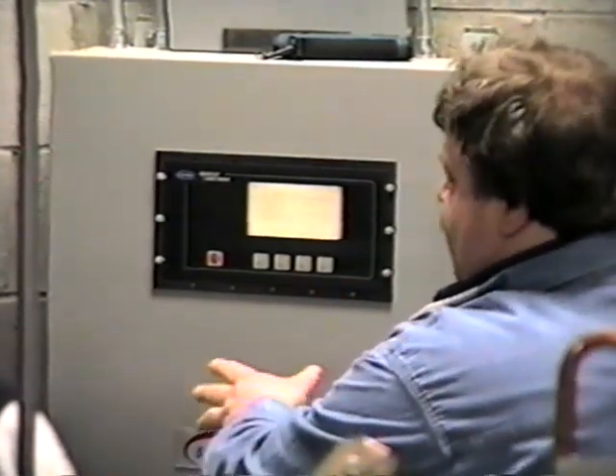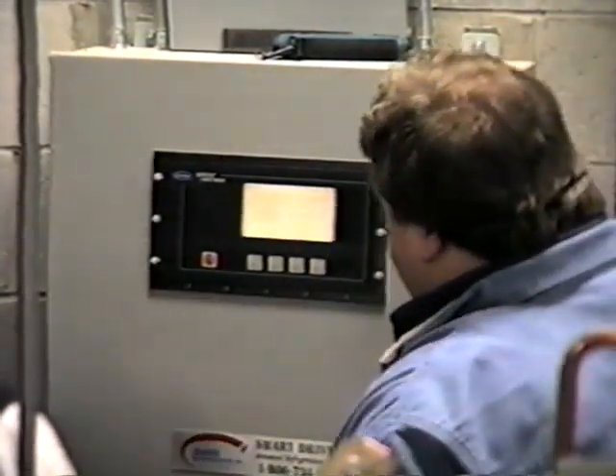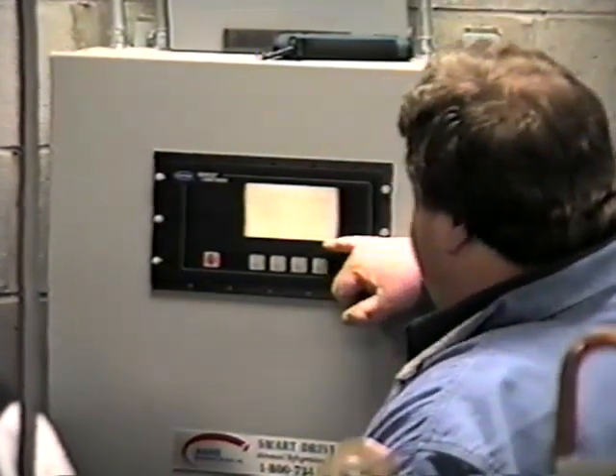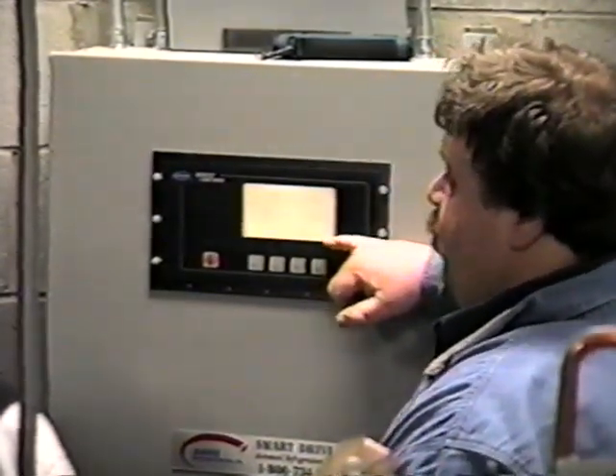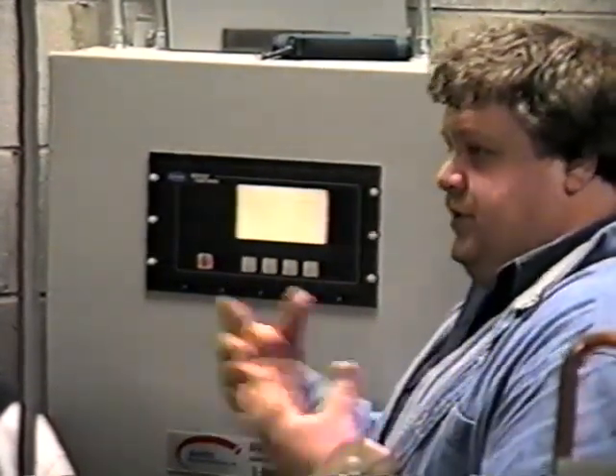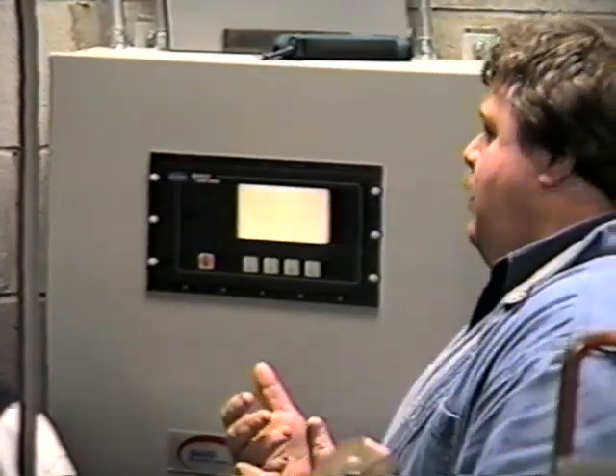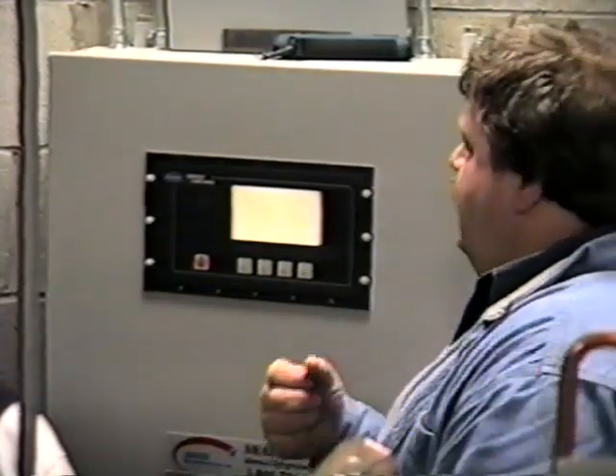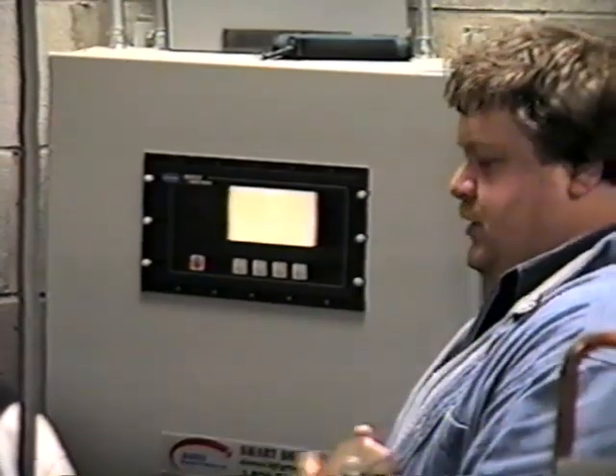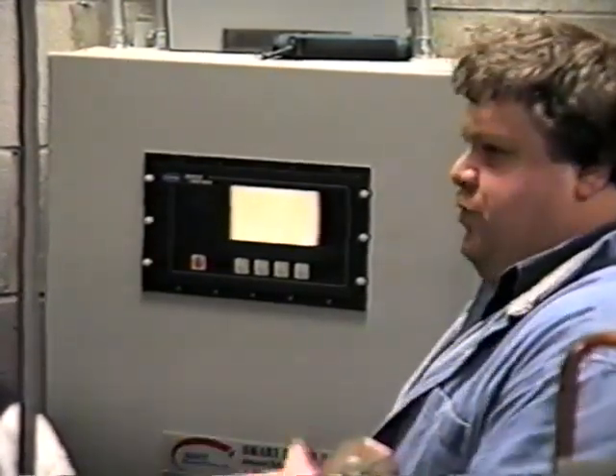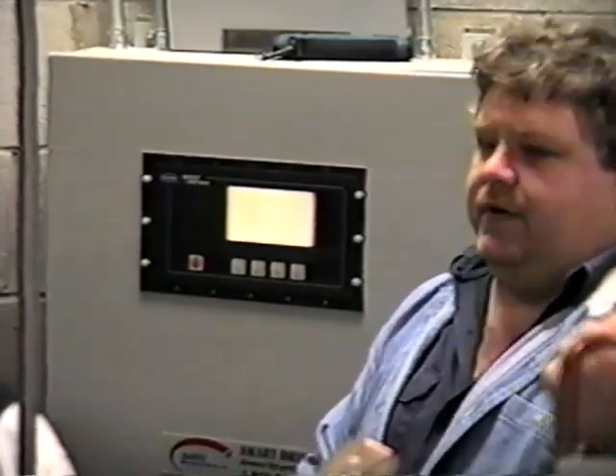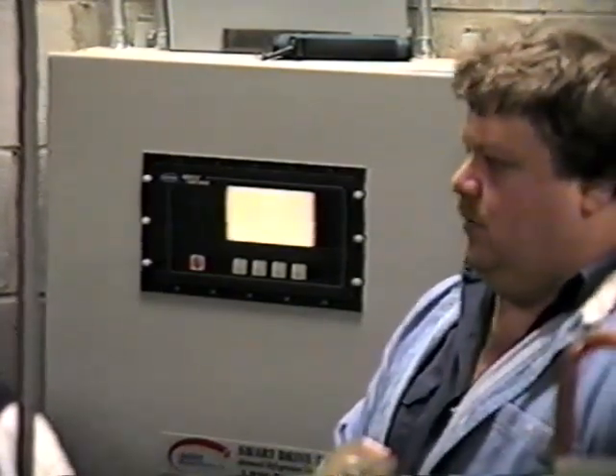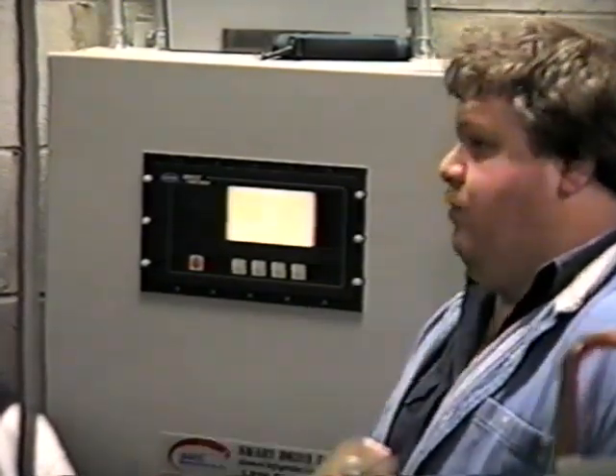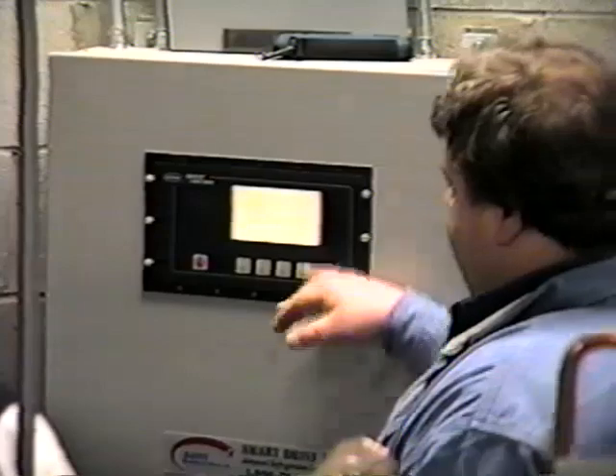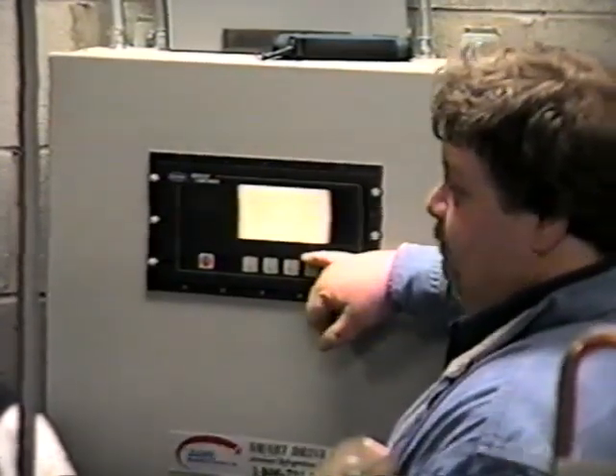This is gonna be very straightforward. There's enough lines of display on here, I believe, for all the items that we have as inputs for temperatures and readback functions, plus all our outputs, which would be to the valve, to the chiller, turn the chiller on, turn the underfloor heat pump on, all that stuff. It should show up on one screen.